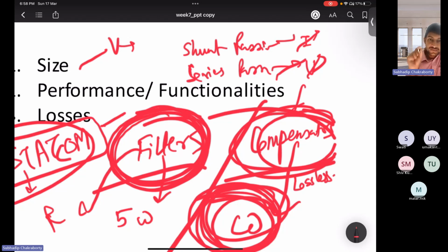So what will happen? For that very small voltage drop, a large current demand from the system may appear. You understand what I am telling? For that particular harmonics, very low voltage will come for a series filter, and then for a shunt, very high current requirement will come because of the low impedance path. So we don't want that, because that will exceed the system current rating.